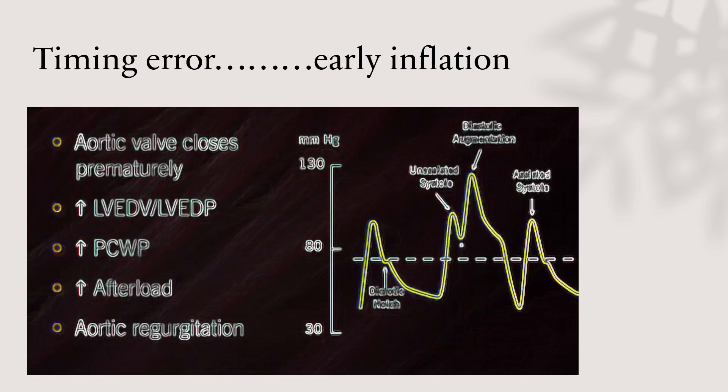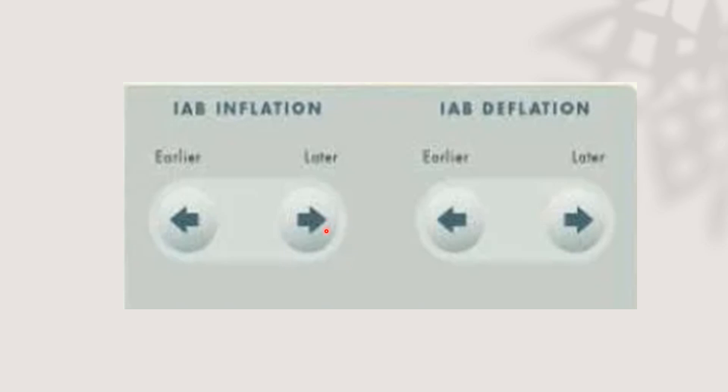As we mentioned before, if a patient has early inflation, it's a timing error. What is the effect on hemodynamics? Early inflation means the aortic valve will close prematurely. Premature closing of the aortic valve increases left ventricular end-diastolic volume and pressure, and all of this will reflect on pulmonary capillary wedge pressure. Also, it increases afterload and exacerbates the presence of aortic regurgitation. If we have early inflation, we will make it late by adjusting on the console till we have the proper curve.